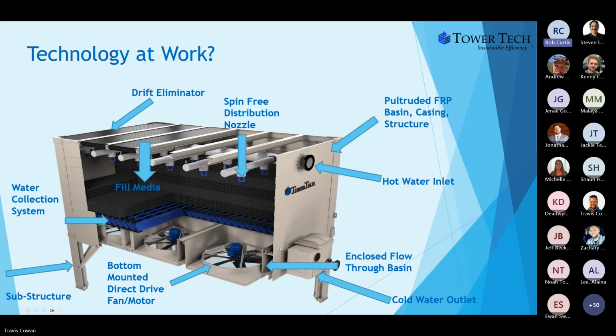Our side-mounted sump box has everything in it that you would go look at. So you'd no longer have to go inside the cooling tower to check your float valve or to clean your suction screen. You just don't have to do it with the TowerTech design. That was important to us, to keep people out of the cooling tower. Then when we move back toward the cooling tower itself, you see the bottom-mounted direct drive fan motor system. This, again, is a little different than what you would traditionally see.